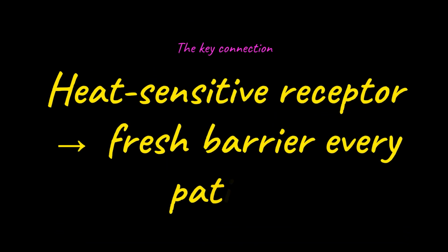The receptor cannot be sterilized, so a barrier steps in where sterilization would otherwise belong, with disinfection as a backup in case of leaks. Linking the receptor's heat sensitivity to the barrier solution is exactly the concept being tested.